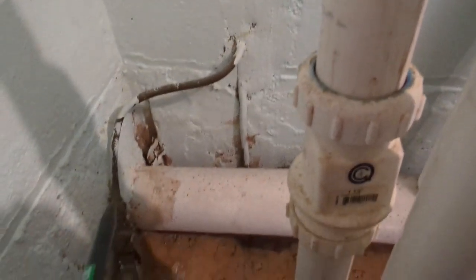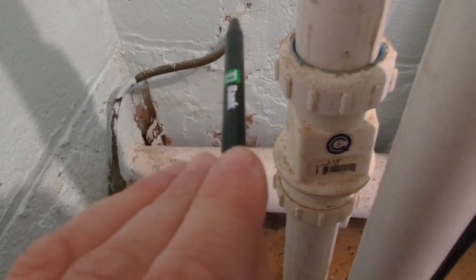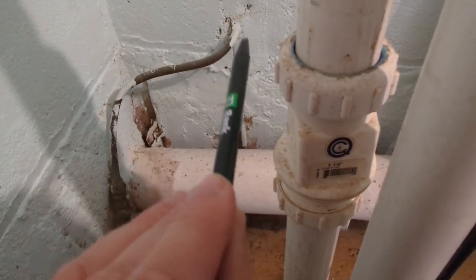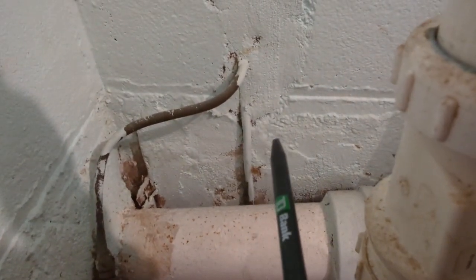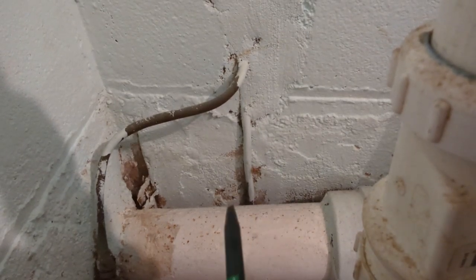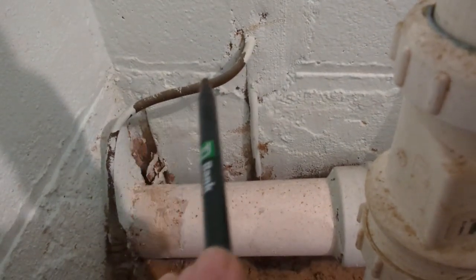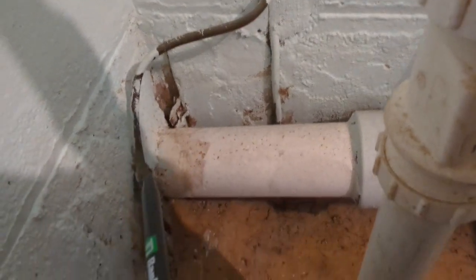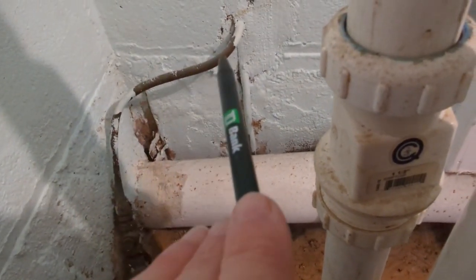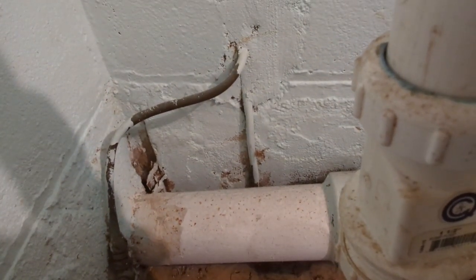They're upstairs taking measurements. So I want to tell them that they should really have a tank sweep performed of this property, because two lines exiting a foundation wall like this generally mean that we had a below ground oil tank on the property. Now, I'm not sure if that's been removed or abandoned or what the situation is, but as home inspectors, when we see this type of thing, these oil supply lines, we have to tell our customer, call that out, and they have to do their due diligence to make sure that there's no oil tanks below ground in this property.